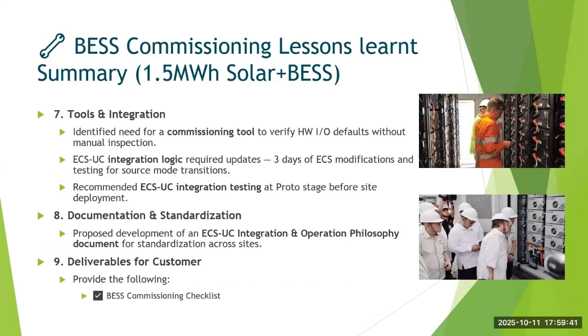The other challenges, the key lessons I learned, were that hardware IO default values, NO/NC contactors, and wiring have to be properly ensured and taken into account. Then we have an EMS and unit controller. We need to ensure that the proper handshake between the EMS controller and the unit controller is happening so that we have proper operation of the BESS.